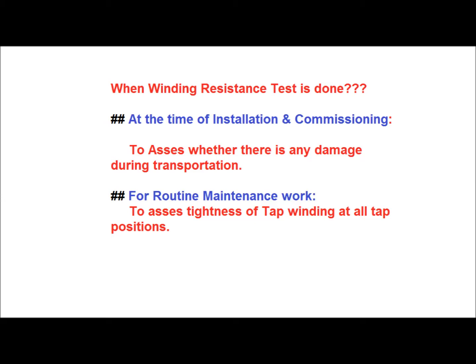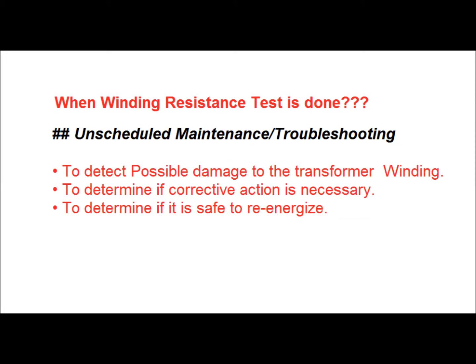Number 2. For routine maintenance work. Since the OLTC is the non-static part of the transformer, it carries the majority of the current during tap changing of the transformer. Therefore, to assess the tightness of the tap winding at all taps, it is recommended to check the DC resistance during routine maintenance work. Also, it is done for unscheduled maintenance or troubleshooting for detection of a fault in the transformer, to determine if corrective action is necessary to rectify the problem and to determine if it is safe to re-energize the transformer after all the testing is done, including the DC resistance test.